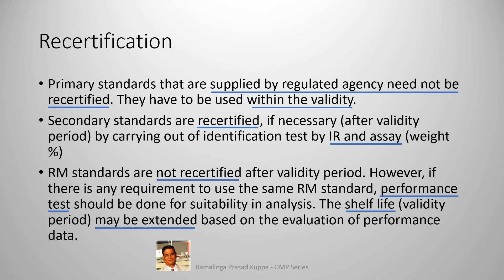Other standards are generally not recertified. If significant quantities of the standard are still available in inventory, it may be tested for its intended purpose by a suitable performance test. If the standard responds without any signs of deterioration or degradation, the shelf life may be extended appropriately.